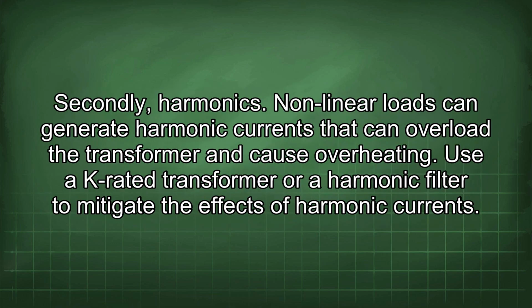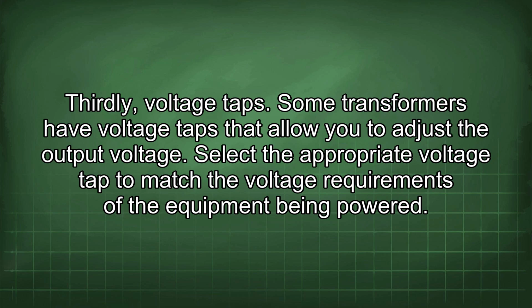Secondly, harmonics. Nonlinear loads can generate harmonic currents that can overload the transformer and cause overheating. Use a K-rated transformer or a harmonic filter to mitigate the effects of harmonic currents. Thirdly, voltage taps. Some transformers have voltage taps that allow you to adjust the output voltage. Select the appropriate voltage tap to match the voltage requirements of the equipment being powered.